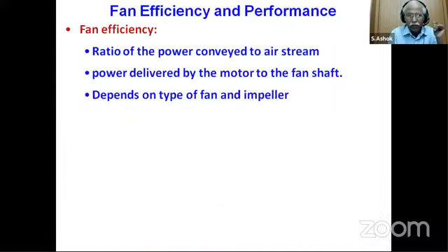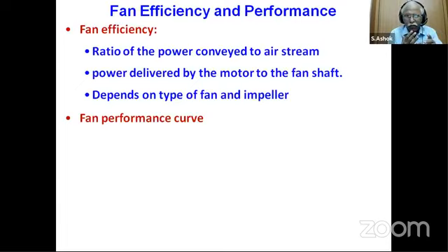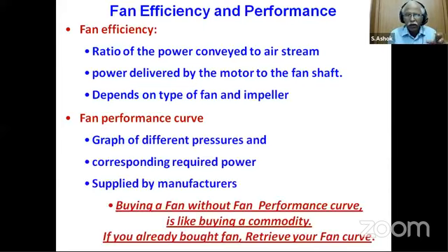So the fan efficiency performance that we see in the AHU is the ratio of the power conveyed to the airstream to the power delivered by the motor to the fan shaft, the blower shaft, and it depends again on the fan and the impeller. The graph of the different pressures is the fan performance curve.